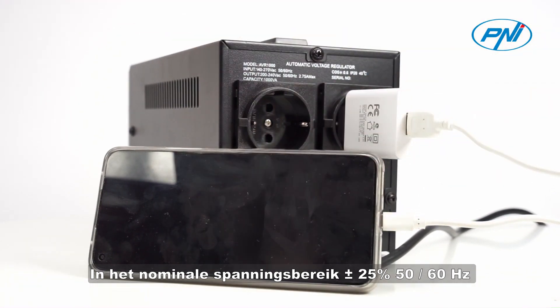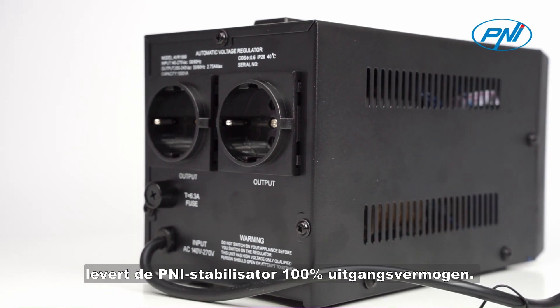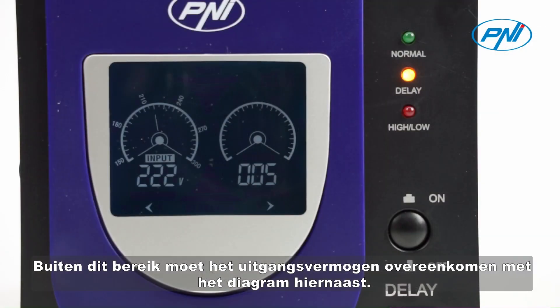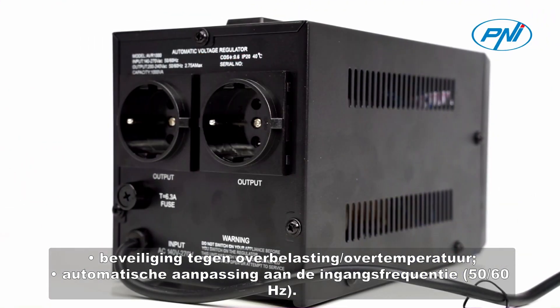In the rated voltage range of plus/minus 25%, 50-60 Hz, the PNI stabilizer provides 100% output power. Outside this range, the output power should be according to the adjacent diagram. Important features include: time delay of 6 or 180 seconds, automatic over-voltage and under-voltage protection (180V–250V), overload and over-temperature protection, and automatic adaptation to input frequency 50-60 Hz.